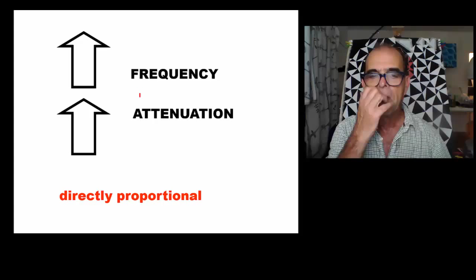Frequency and attenuation are directly proportional. The higher the frequency, the more attenuation the ultrasound suffers. In other words, a high frequency transducer has high attenuation, in other words, low penetration. High quality, high attenuation, low penetration, cannot penetrate deep organs. Attenuation and half value layer thickness are inversely proportional. The more the attenuation, the less the half value layer thickness, and this is the reason a high frequency transducer has a high attenuation but a low half value layer thickness.